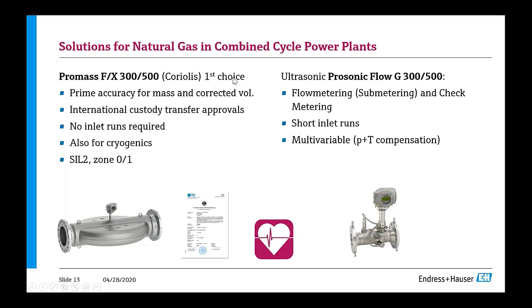So the first choice when it comes to natural gas in a combined cycle power plant at the custody transfer measuring station, from my perspective, is a mass flow meter like our ProMass F or X. You get the best accuracy there is on the market. You don't need compensation. You directly get the mass and you divide by the reference density from your gas chromatograph. It's a no-brainer, even though you may have a custody transfer ultrasonic that has on paper a relatively good accuracy, because then you have to add the uncertainty of the pressure, temperature, and also the gas composition, and all of a sudden you have much higher uncertainties than what you get with such a solution.